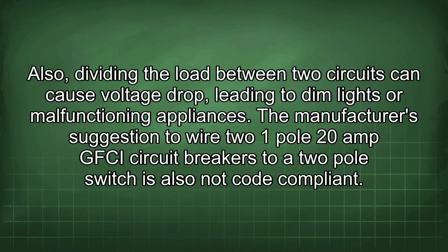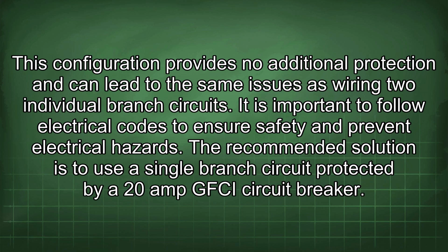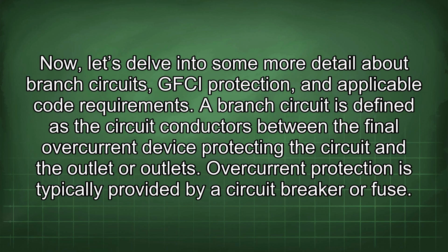The manufacturer's suggestion to wire two one-pole 20 amp GFCI circuit breakers to a two-pole switch is also not code compliant. This configuration provides no additional protection and can lead to the same issues as wiring two individual branch circuits. It is important to follow electrical codes to ensure safety and prevent electrical hazards. The recommended solution is to use a single branch circuit protected by a 20 amp GFCI circuit breaker. Now let's delve into some more detail about branch circuits, GFCI protection, and applicable code requirements.